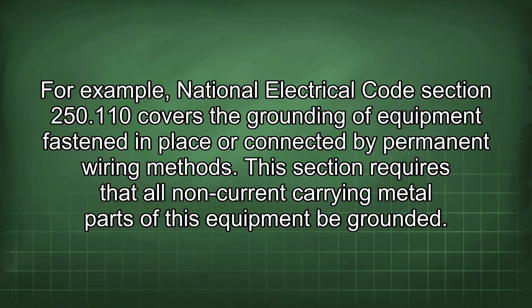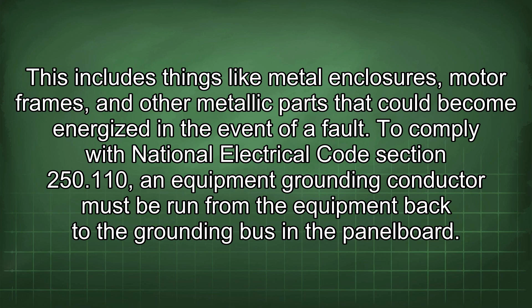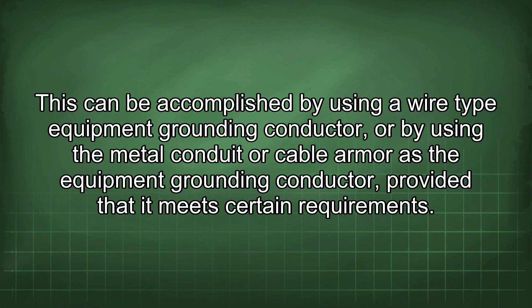To comply with National Electrical Code Section 250.110, an equipment grounding conductor must be run from the equipment back to the grounding bus in the panel board. This can be accomplished by using a wire-type equipment grounding conductor, or by using the metal conduit or cable armor as the equipment grounding conductor, provided that it meets certain requirements.